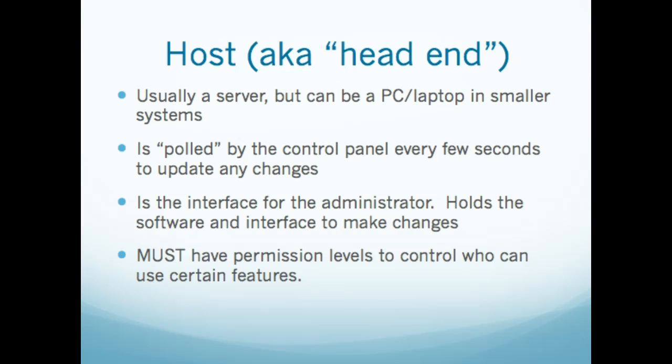It's polled by the control panel every few seconds. Essentially, the control panel is jumping back up to the host saying, got anything new for me? Yes, no. Got anything new for me? Yes, no. Every couple seconds. It just keeps asking for any updates or changes because there's an administrator sitting there, and in a very active, large system, they're making changes all the time.